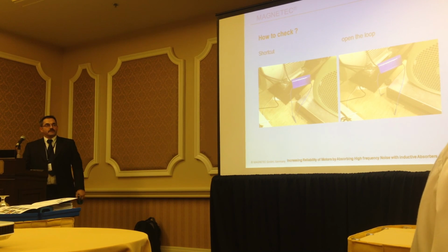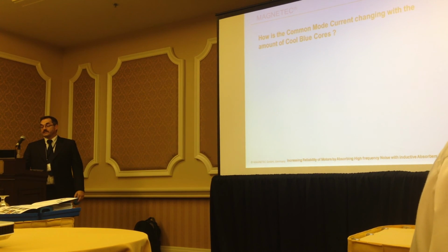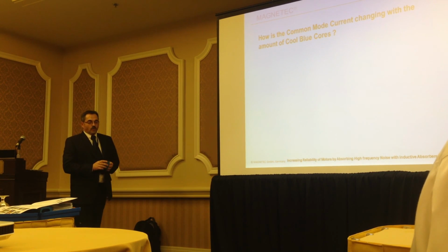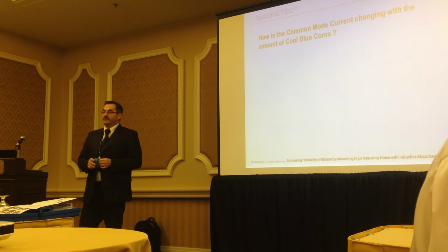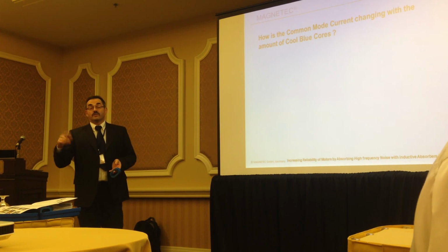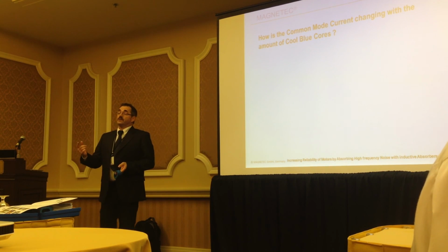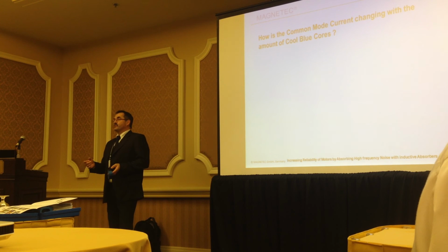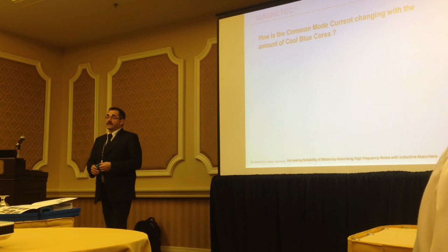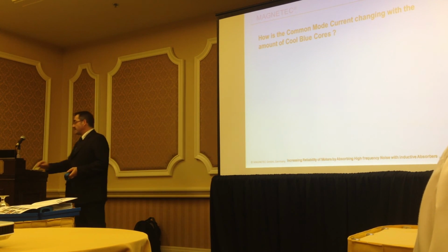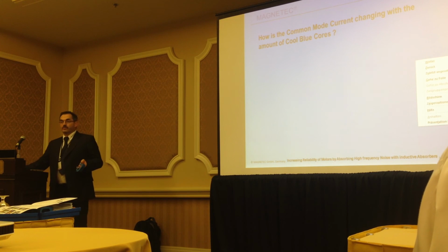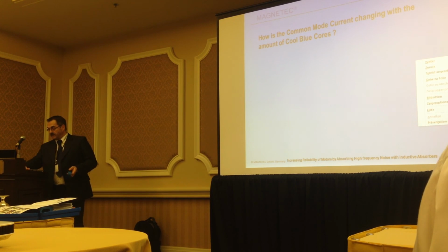There's something very interesting - we're working together with universities. There's a factor called 0.3 amps per square millimeter. This is the maximum allowed current over the motor bearing. If you exceed that, no bearing producer gives you a guarantee on the standard lifetime. This is a bit of a complex thing, but we can talk about it at the booth if you want.